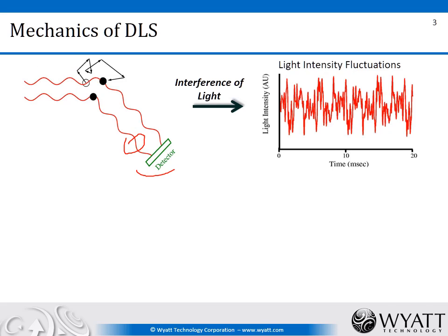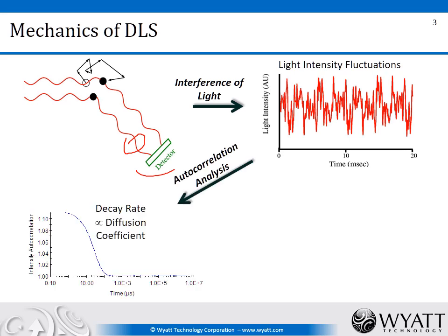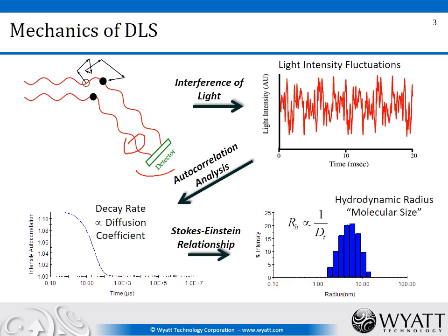Over time, as we measure the light scattering over timescales of microseconds to milliseconds, we see intensity fluctuations which essentially look like noise. Fortunately, that noise contains useful information: the rate of diffusion of the particles, which is related to their size. We perform autocorrelation analysis, which gives us the rates of fluctuations in the light scattering intensity. This can be fit to determine a diffusion coefficient, which is converted to the hydrodynamic radius using the Stokes-Einstein relationship, and the size and distribution of sizes can be determined.